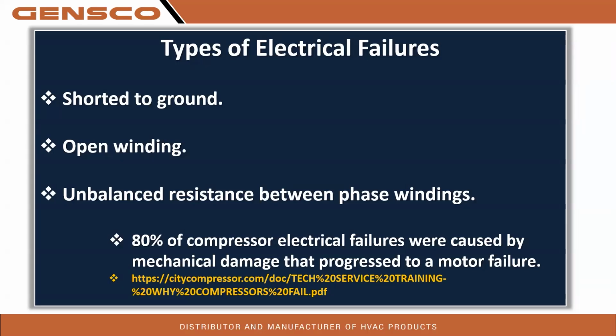And another question was, why is the crankcase heat not cut from the factory? Efficiency ratings. It's going to steal power. In the case of some of the units, it could be 50 watts of power is used to crankcase heat that compressor. So that can have a significant effect, 50 watts when a unit's not running, on its overall efficiency rating. And we want to be able to sell this unit based on its efficiency rating. So that is why it's not cut from the factory. Now, when it gets to the homeowner, does he care if his efficiency went down slightly, if it keeps his compressor running? Well, that is why it's not cut from the factory.